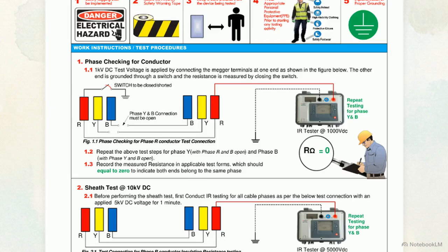Test 13-1 verifies phase checking and sheath integrity. 1 kV DC is applied from a megger at the phase R conductor. The far end switch is closed. Zero resistance proves continuous identity end-to-end. Repeat for Y and B phases.